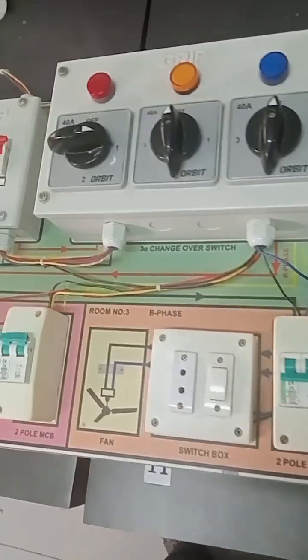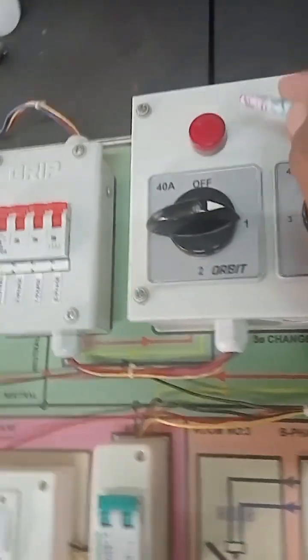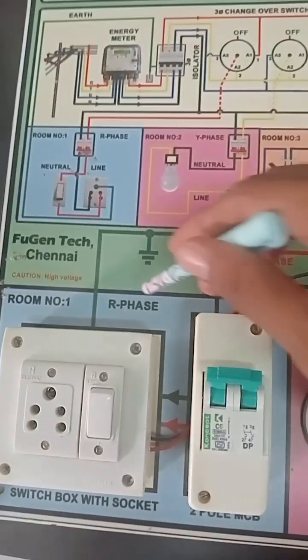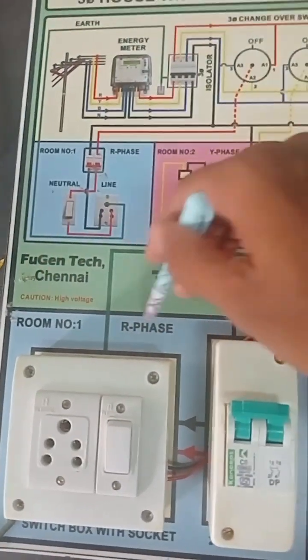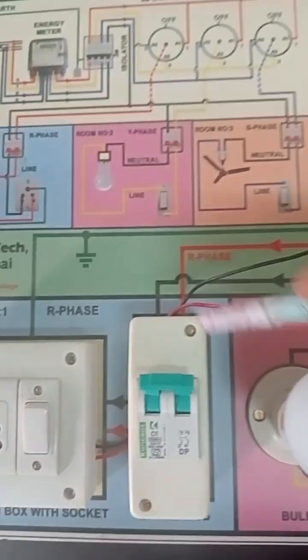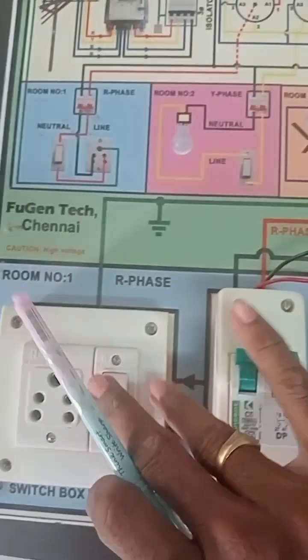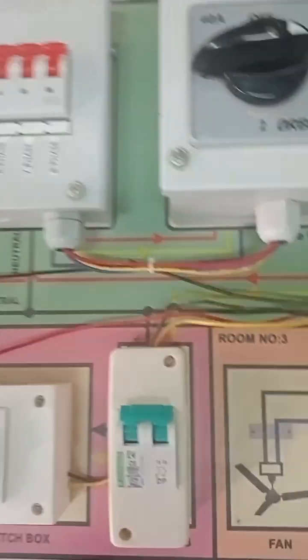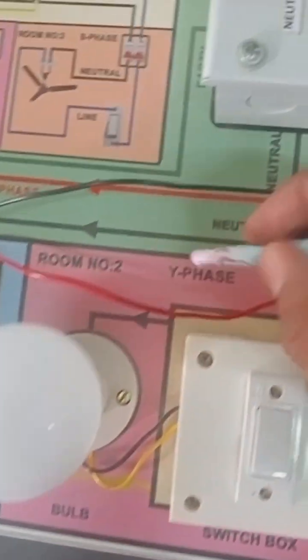Okay, it is mandatory, only then can we connect the red phase to room 1. You can see room 1 on the red phase. For the sake of understanding, there is a miniature circuit breaker available, and a specific switch box. So with the Y phase itself, we are connecting room 2.